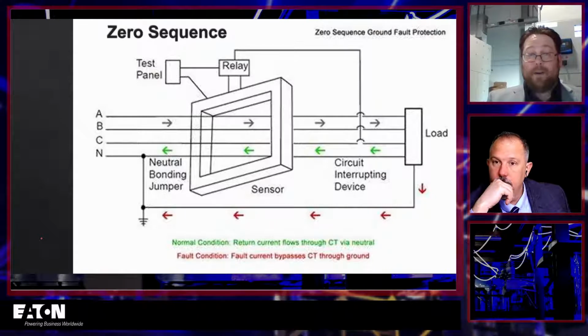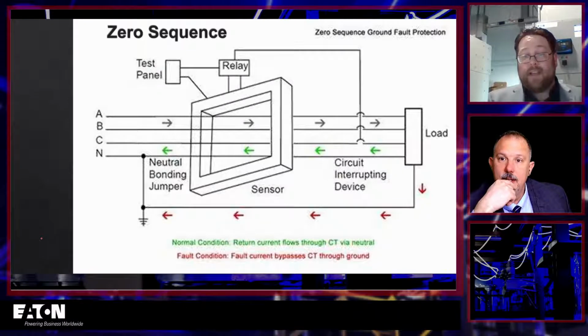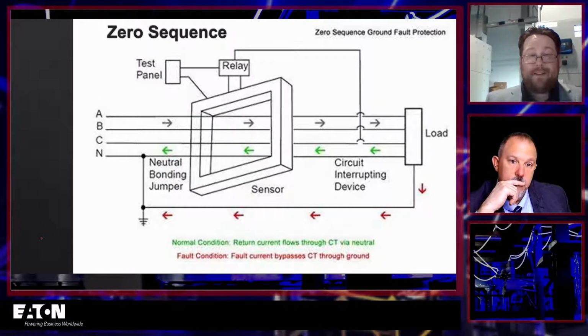Yep. So we're flowing current through your phase sensors, through the breaker and then back out. We need to test it, two tests here, really. Phase A, the normal situation where we should have no trip. And then we need to take the current around that neutral conductor, through another path outside of the sensor, and confirm that it does trip appropriately.